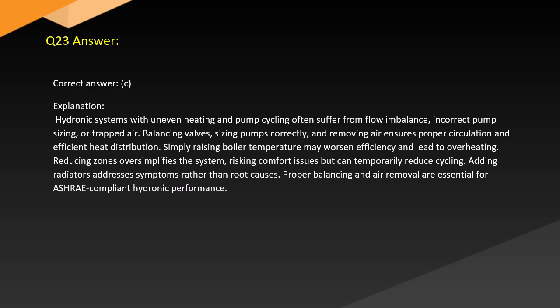Answer. Correct answer: C. Explanation. Hydronic systems with uneven heating and pump cycling often suffer from flow imbalance, incorrect pump sizing, or trapped air. Balancing valves, sizing pumps correctly, and removing air ensures proper circulation and efficient heat distribution. Simply raising boiler temperature may worsen efficiency and lead to overheating. Reducing zones oversimplifies the system, risking comfort issues, but can temporarily reduce cycling. Adding radiators addresses symptoms rather than root causes. Proper balancing and air removal are essential for ASHRAE-compliant hydronic performance.